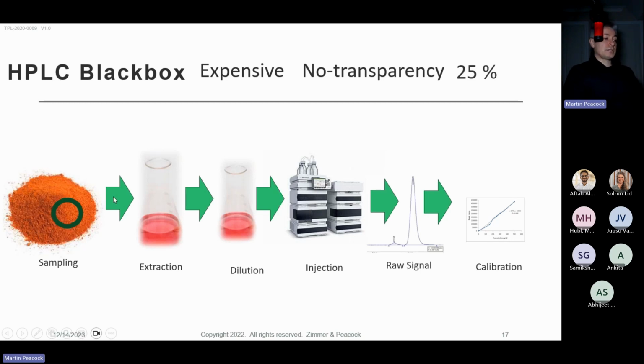And when you've got processes like this, so there's 1, 2, 3, 4, 5, at least 5 processes going on here, every time you have a process, there's an error associated with it. These errors can stack up, but you have no sense. I've just said here, well, if each process had an average, let's say, error of 5%, by the time you've got 5 processes, you've got an error of 25%, or a range. So you get a result from the HPLC, but that's actually plus or minus 25%.